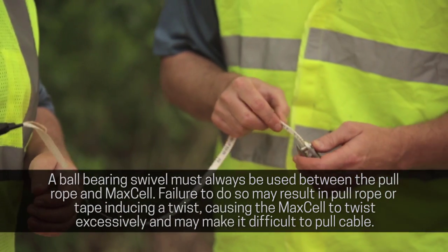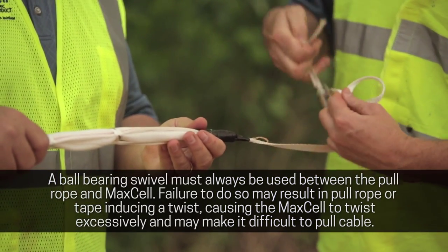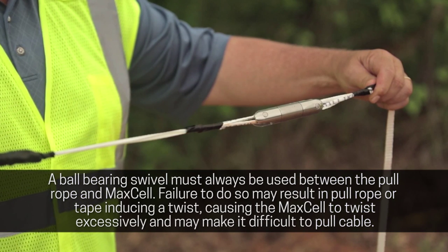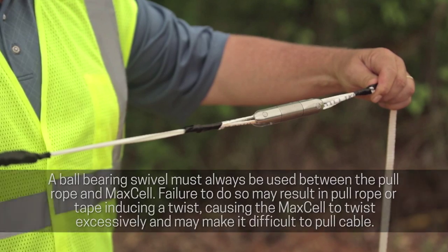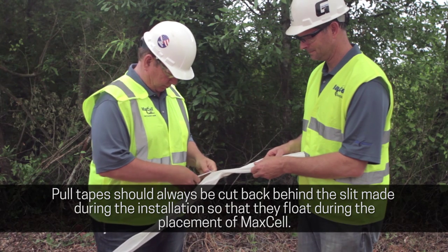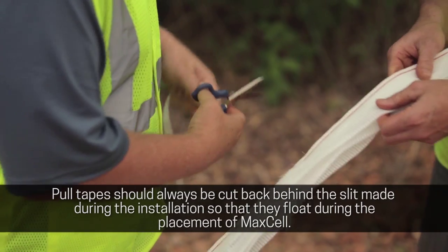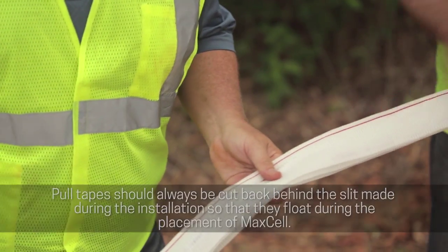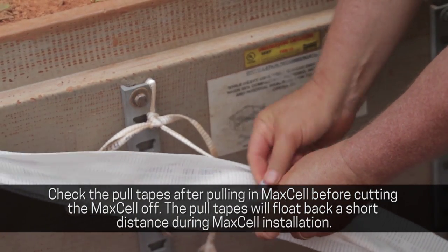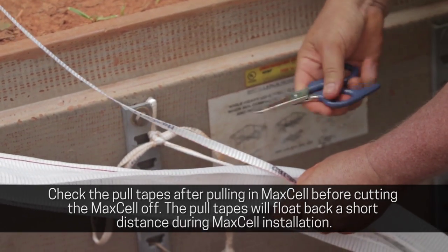A ball bearing swivel must always be used between the pull rope and MaxCell. Failure to do so may result in the pull rope or tape inducing a twist, causing the MaxCell to twist excessively and making it difficult to pull cable. Pull tapes should always be cut back behind the slit made during the installation so that they float during the placement of MaxCell. Check the pull tapes after pulling in MaxCell before cutting the MaxCell off — the pull tapes will float back a short distance during MaxCell installation.